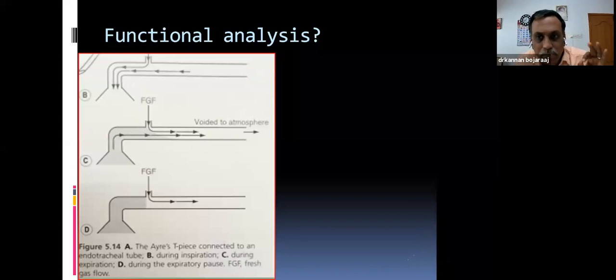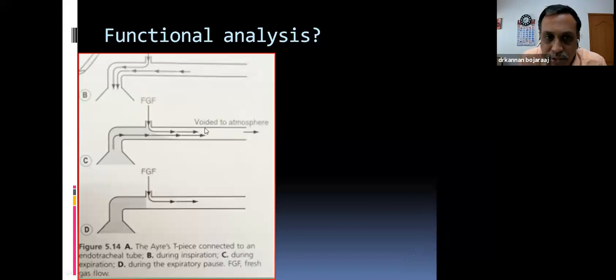So during the period of expiratory pause only, the fresh gas flow will vent out all the gases present in the expiratory limb. The diameter of this reservoir limb must be sufficient to present the lowest possible resistance to the pediatric patient. The diameter should give the lowest resistance possible, and for the neonate, the resistance should be less than 1 centimeter of water.